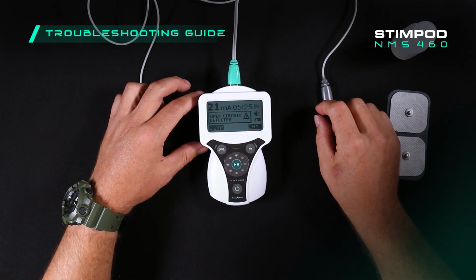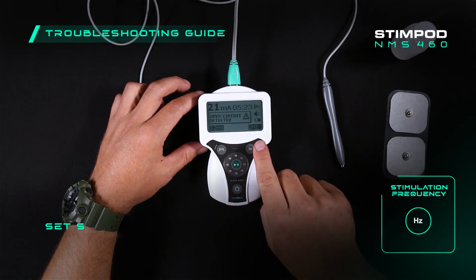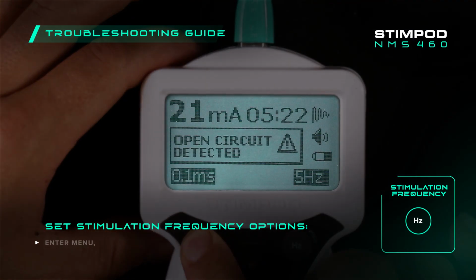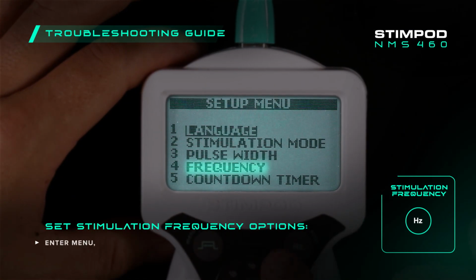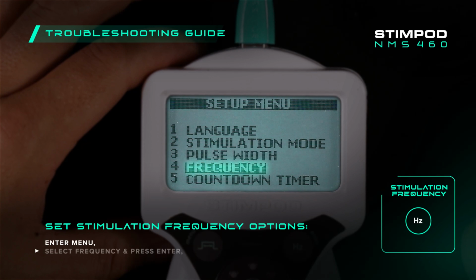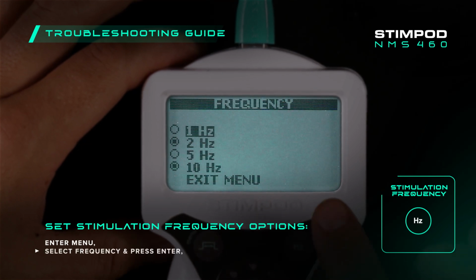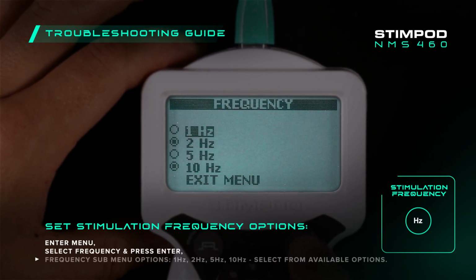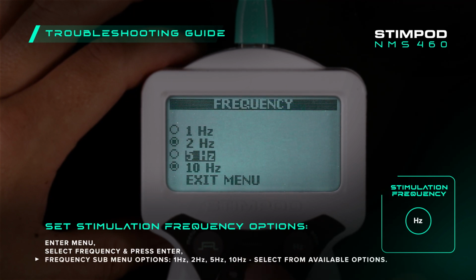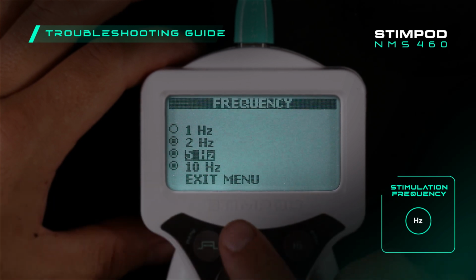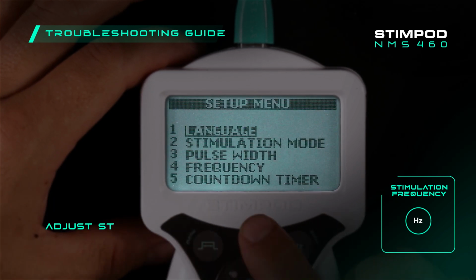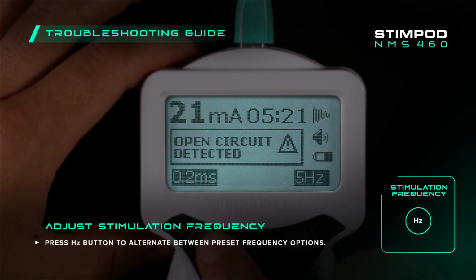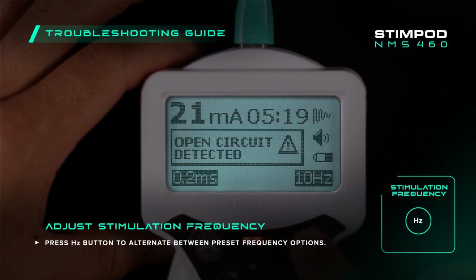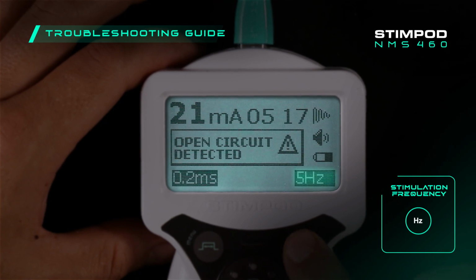You can adjust the stimulation frequency in the Stimpod menu. Press and hold the menu button and use the touch wheel to scroll down to option 4, Frequency, and press Enter. The frequency submenu will appear. There are 4 options you can choose to have active: 1, 2, 5, and 10 Hz. Activating these options in the submenu will grant you the option of alternating between them on the home screen by pressing the frequency button.